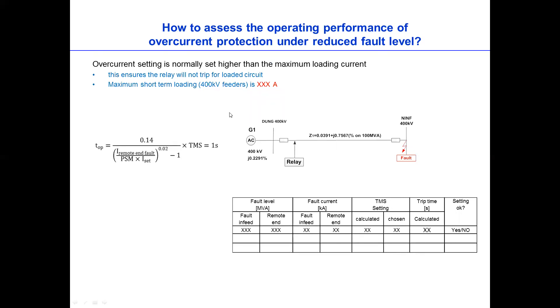So the conventional distribution setting is okay because we used to have strong inertia or high fault current contribution from coal-fired power station or strong generators. But now the problem is how do we achieve when the fault level is reduced? So for example, normally we set overcurrent protection higher than the maximum loading current because this will ensure the relay will not trip for loaded circuit.